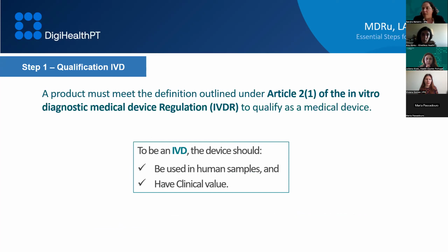Regarding the IVD, the same thing should be done. They have similar procedures to qualify the product as an IVD. So an IVD must be for human sample use. If it's for animals, for instance, it is not an IVD and could not be an IVD. And these tests should have a clinical value. Okay, they have to have importance regarding the diagnosis of a disease or screening of a disease. This is very important for us to qualify the product as an in vitro diagnostic medical device.